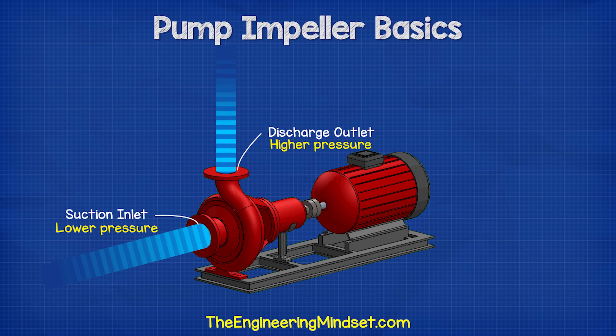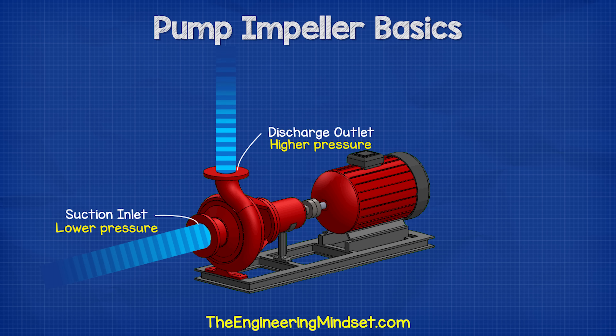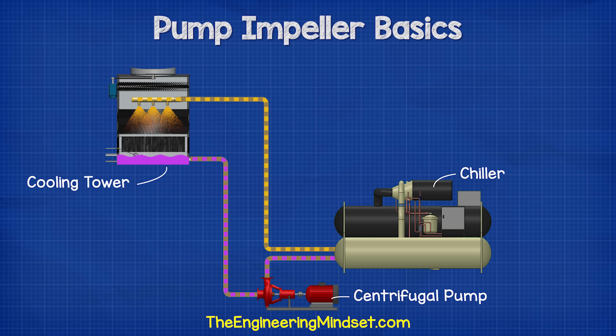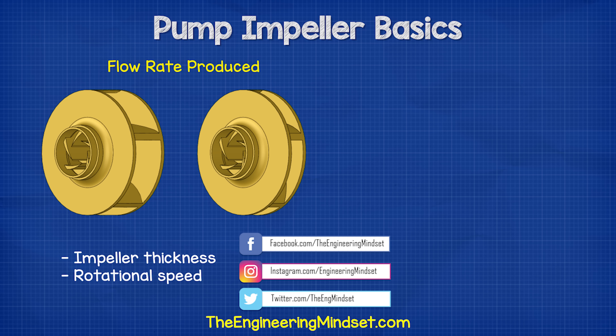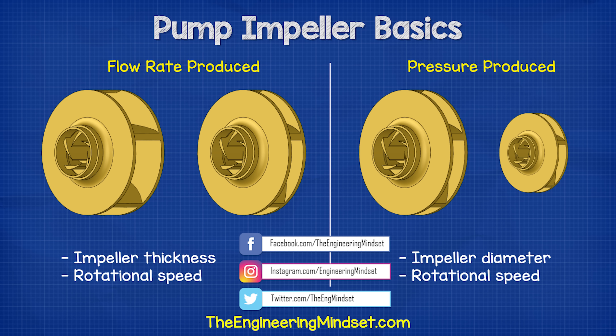So the discharge outlet is therefore at a higher pressure than the suction inlet. The high pressure at the discharge allows us to force the fluid through pipes and into a storage tank or around a pipe system. The thickness of the impeller and the rotational speed affects the volume flow rate from the pump, but the diameter of the impeller and the rotational speed will increase the pressure it can produce.